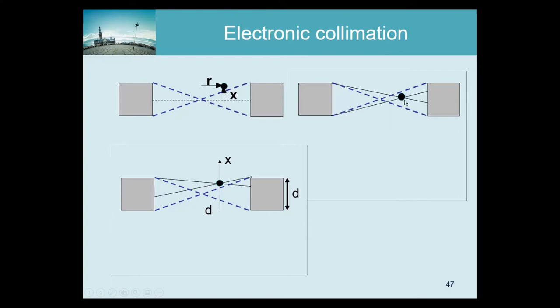Another question is: what happens if I put a point source exactly in the middle — what sensitivity do we have? How to compute it: for symmetry, if one photon hits the crystal, the other photon emitted in the opposite direction will also hit the crystal. So we can look at one detector and compute d squared divided by the radius squared, then times two because there is a detector on the other side.